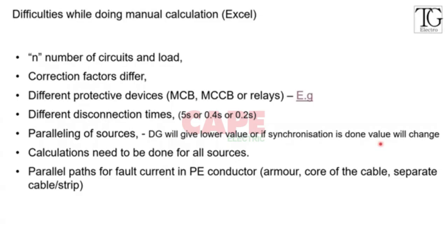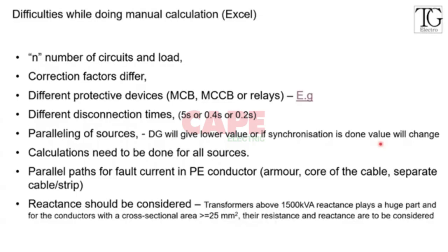And the other main problem is if you have parallel fault current. If you're using armoring as a fault PE conductor, or if you're using a GI strip as a PE conductor, then there are going to be two parallel paths. So that is also a problem. That is going to increase the current and decrease the resistance if you have a parallel path.